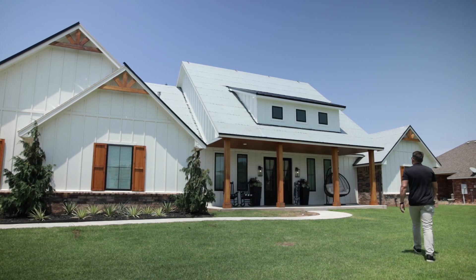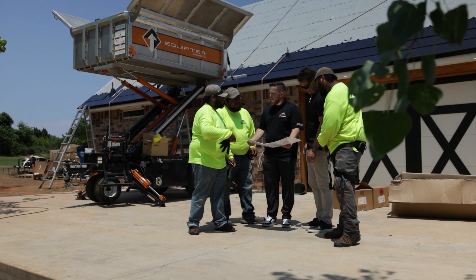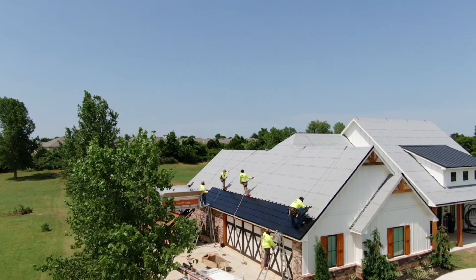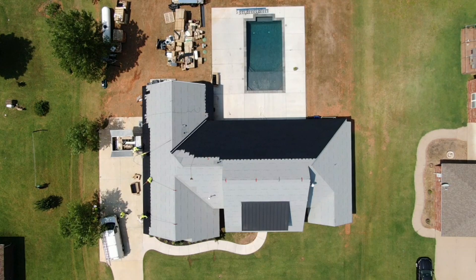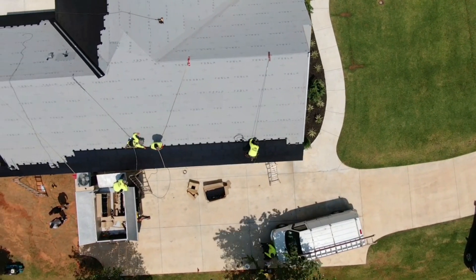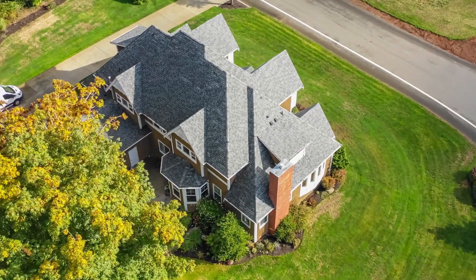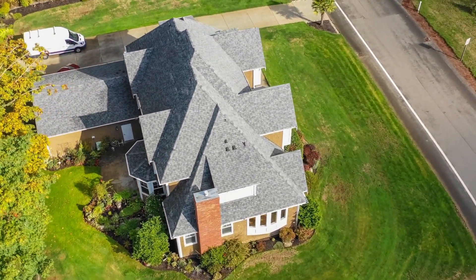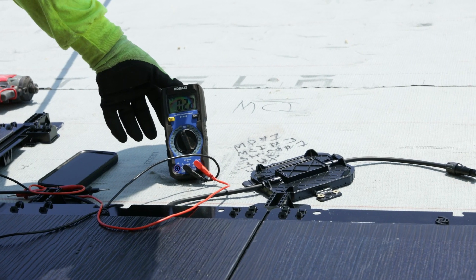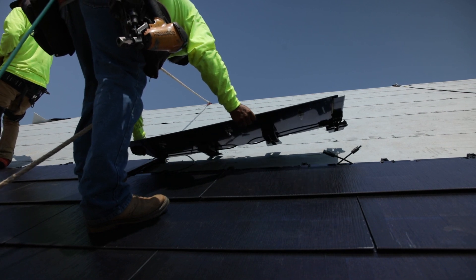A good solar roof candidate needs a simple roof with simple slopes. The direction the slopes are facing is important — east, west, and south exposure are ideal, while north exposure is not always the best since some areas don't get much sunlight during certain times of year. We're looking for large, simple roof planes — rectangles. The more cut up a roof is, the less suitable it is. Obstructions, valleys, hips, and chimneys all take away our ability to put together strings of photovoltaic panels or solar arrays. So simple is actually better.